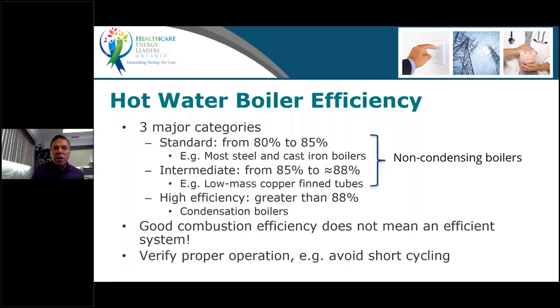Then you've got mid efficiency, 85 to about 88. And then you've got the high efficiency, the condensing boilers, and that's above 88% efficiency. If you see a boiler that has an efficiency above 88%, typically 90, 93, 95%, right off the bat, you know it's condensing. The reason is there's about 12% of the energy in the flue gas, in the combustion gases, that is water vapor. And in order to get more than 88% efficiency in a natural gas boiler, you need to condense. So you're a condensing boiler, so you can capture that latent heat that's in the water vapor.